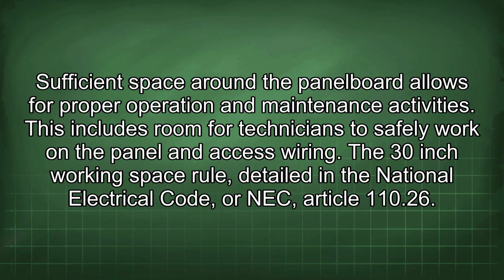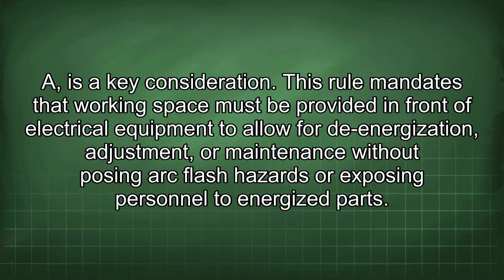The 30-inch working space rule, detailed in the National Electrical Code, or NEC, Article 110.26(A), is a key consideration. This rule mandates that working space must be provided in front of electrical equipment to allow for de-energization, adjustment, or maintenance without posing arc flash hazards or exposing personnel to energized parts.